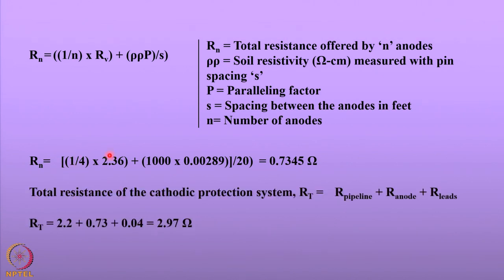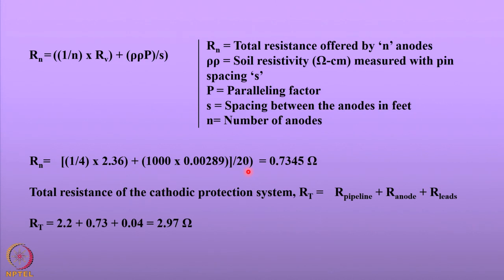Once we know the anode ground bed resistance, the total resistance of the cathodic protection system — consisting of pipeline, anode, and leads — is calculated. The pipe-to-soil resistance and lead resistance are known; the anode ground bed resistance has been calculated. The total resistance offered by the system is 2.97 ohms. Our next task is to determine whether the zinc anode can drive the current against this resistance.